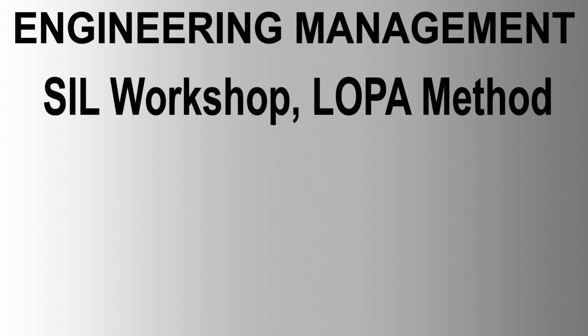SIL determination methodology. Steps to determine a safety function SIL rating based on IEC 61511. 1. Perform a hazard and risk analysis. 2. Identify required safety functions. 3. Allocate safety functions to independent protection layers. 4. Determine if a SIF is needed. 5. Determine the required SIL of the SIF.